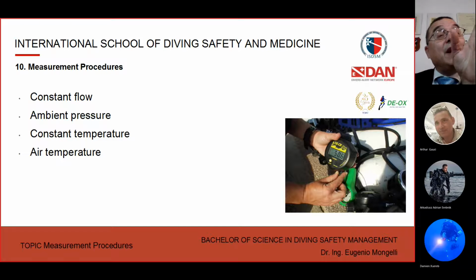So always be careful with the temperature, okay, mainly in summer, because when you are in summer you forget the analyzers under the sun. Then the sensor inside is 40 degrees, 50 degrees, then you go on the cylinder, and the gas coming out of the cylinder is 15 degrees, and then you have a mess. Oh my God, the sensor is not working well. I have 3%, 4% error. Or worse, you go and then you call the blender of the diving center.